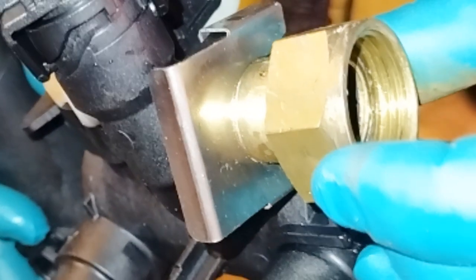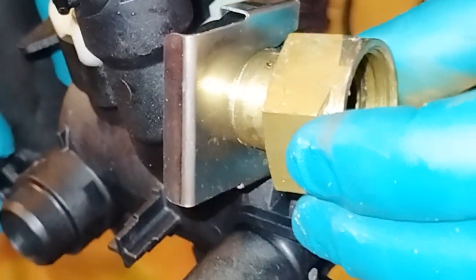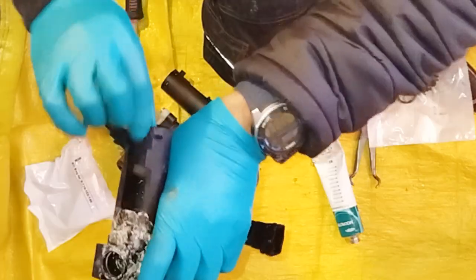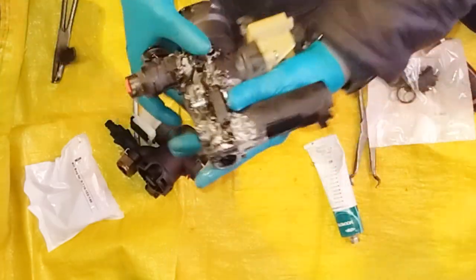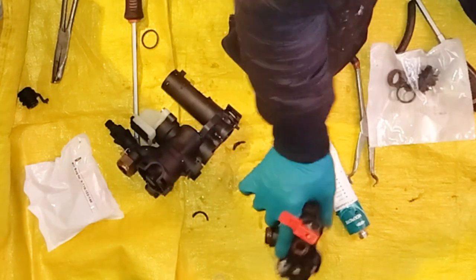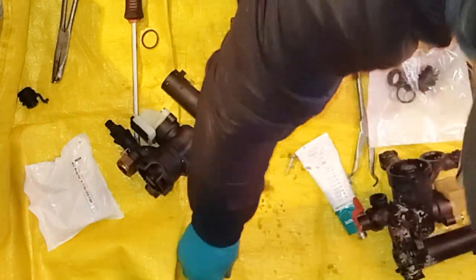This is, as you can see, the inside of the collar is sitting right next to the brass, so there shouldn't be any distance or any space between the clip and the brass connection. So to remove the old flow turbine adapter, it always breaks. Part of it is left inside, part of it goes outside. So this is the old one. It breaks where the nut normally sits on this assembly.